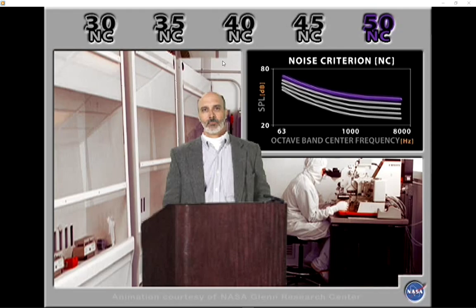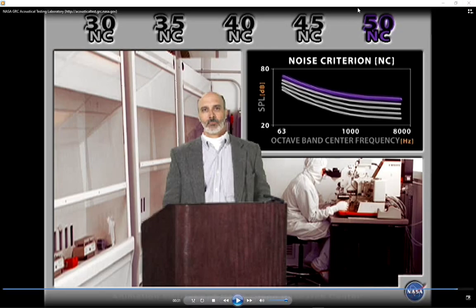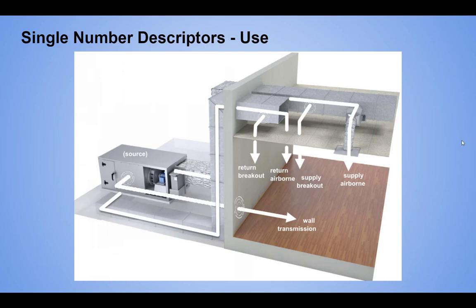NC is useful when working with a client. For example, if you need to move mechanical equipment away from an acoustically sensitive room to bring background noise to a proper level for education, you can say: your existing classrooms are NC 35 right now — very quiet background noise for a classroom — but the cost-saving approach raises that up to NC 50. You can use those objective measures to make the case.